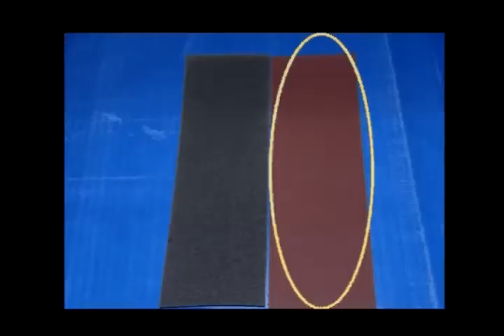With 400 mesh abrasive paper, grind around the probe, the 120 mm long front end part, removing the black oxides on the surface. Grind circumferentially, polishing until metallic luster appears. Then use 600 mesh abrasive paper in the same way on the front end of the probe for surface treatment. Keep in mind that grinding must be in the circumferential direction, or the life of the probe and the data accuracy will be affected.